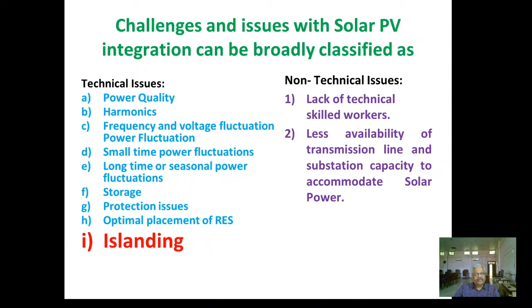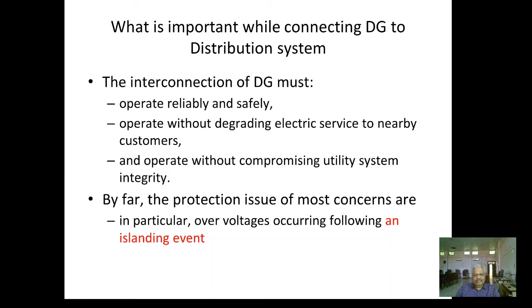Okay. Now what is important while connecting distributed generation to the distribution system? The interconnection of distributed generation must operate reliably and safely. Of course, this is very important. Whenever any interconnection is there, it must be reliable, and the safety concern is there. Then this interconnection must operate without degrading electrical service to nearby customers. Everyone will expect this. This interconnection must operate without compromising the utility system integrity. We'll see these things slowly in the next slides. By far, the protection issue of most concern is, in particular, over voltages occurring following an islanding event. The main issue is the protection issue, and why this issue is there, because there are over voltages occurring following an islanding event. And what is this islanding event?